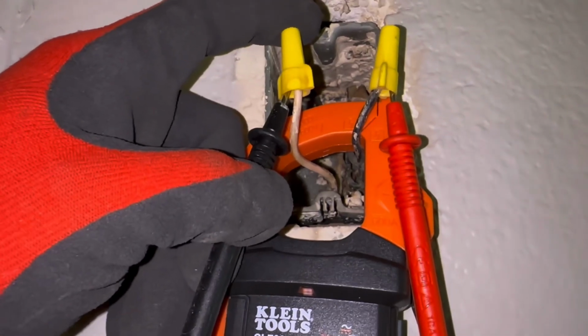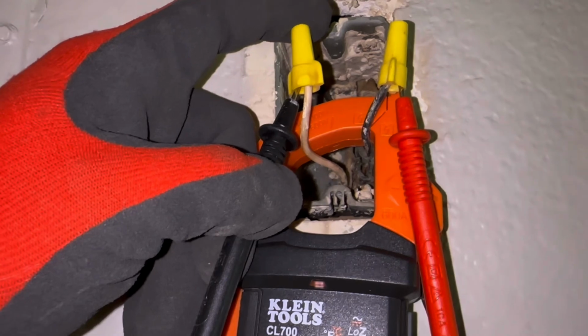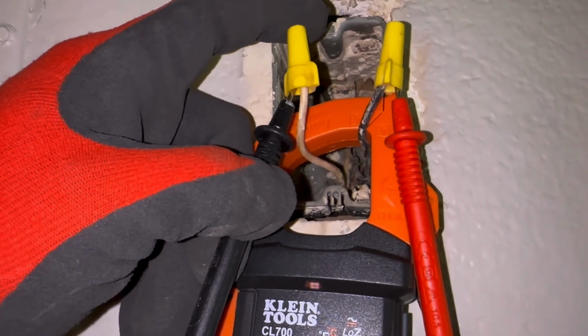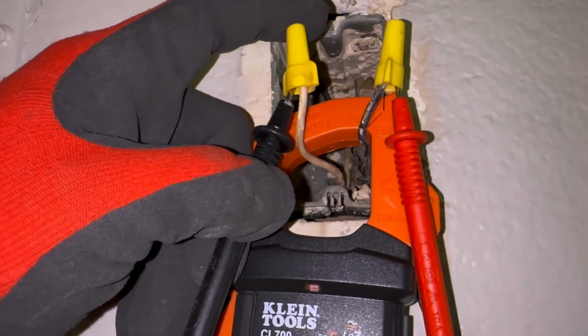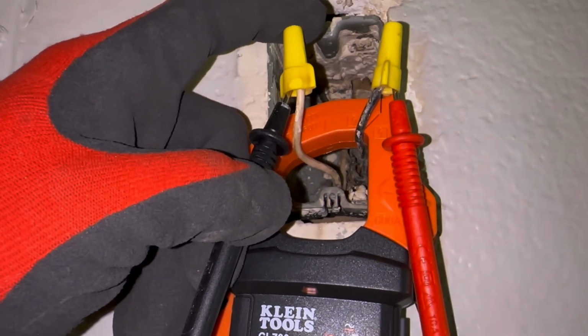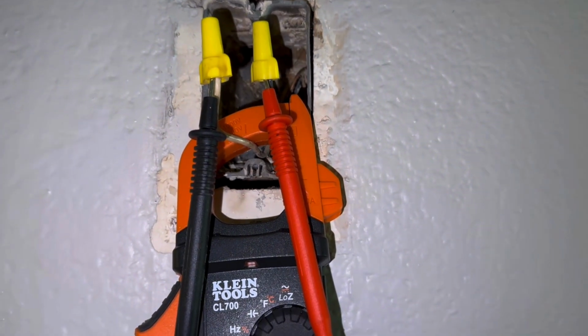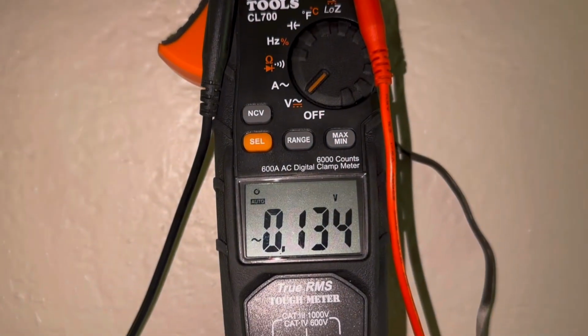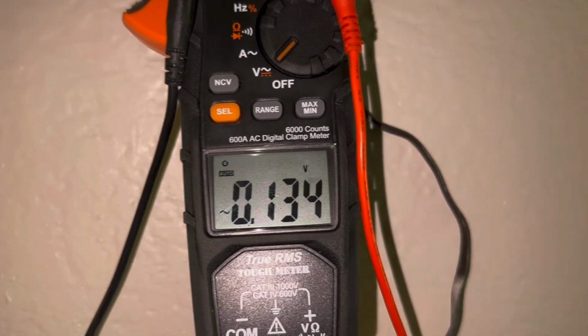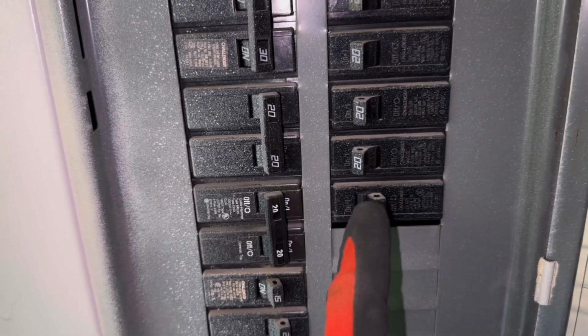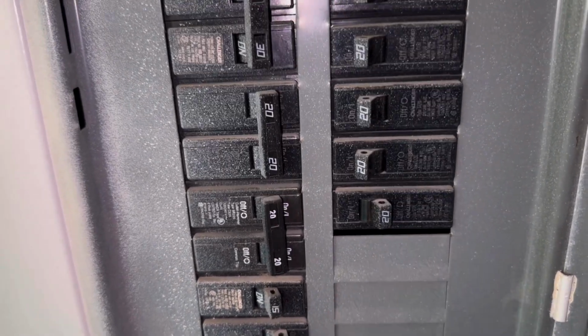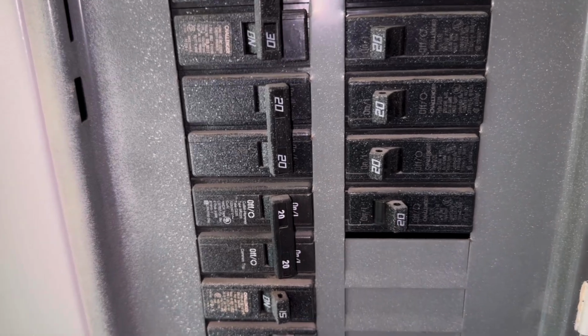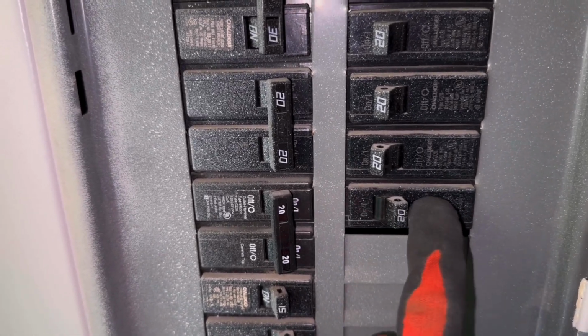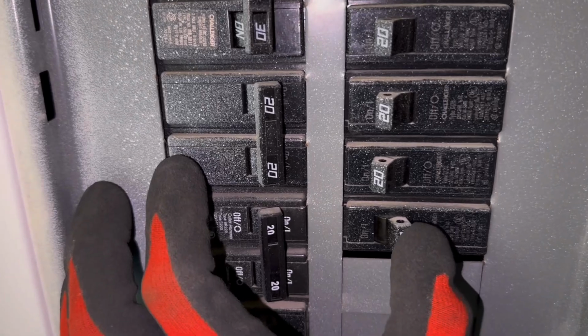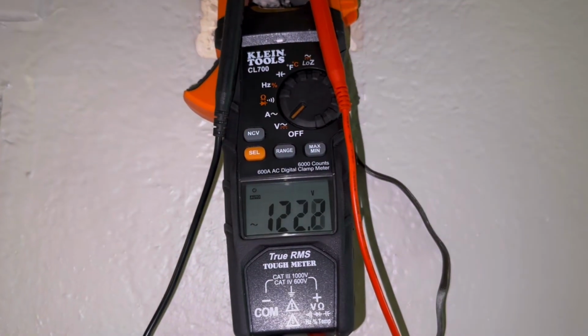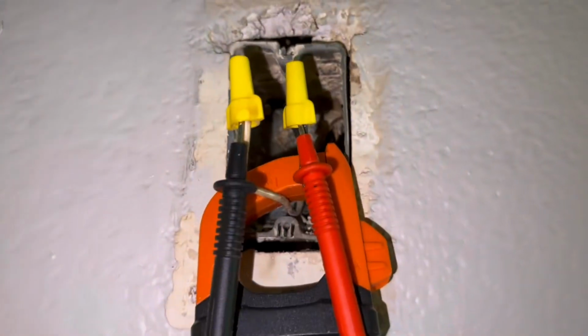If you're not getting voltage from these wires, this would indicate that you're having issues at the circuit breaker. The circuit breaker would not be sending the voltage here to the transformer. If you have your multimeter connected and you're not getting any voltage reading, you would go to the circuit breaker panel. It's possible that there is a tripped breaker. Just for this video, I turned the breaker for that smoke detector to the off position. And what you would do is reset that breaker, or turn that breaker back on, and that should send 120 volts back to your lines.